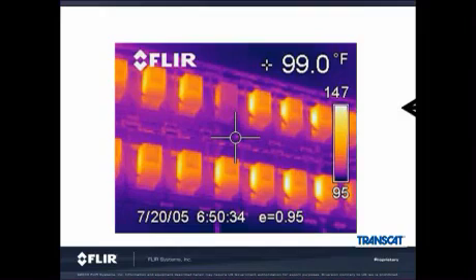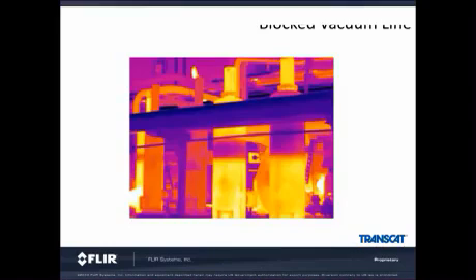In this picture, we again see many components doing the same work. And by temperature differential, we're able to see which one is not on. It's the one in the middle. And the reason why we know that is because it's not creating any heat. That's right. Not everything fails because it's hot. Sometimes things don't turn on, and you can see that by their lack of heat. So thermal imagers are as good at finding targets that have a lack of heat as those that have too much. Therefore, the operator, by using the thermal camera, was able to quickly find the faulty transformer and get the repair going quickly.